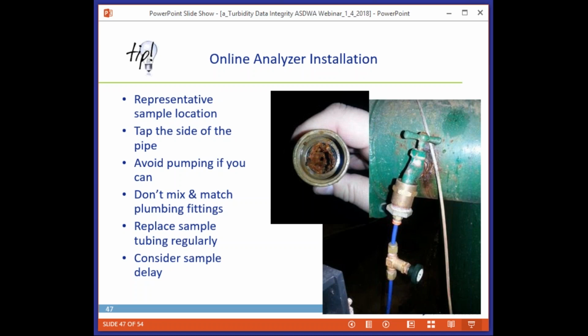Tapping the side of the pipe is clearly recommended over the bottom, where you may get sediment, but even more importantly than the top of the pipe, where you tend to get air accumulations, which can lead to some erroneous turbidity readings. If you can, it's ideal to avoid pumping. That's not always an option for people. Don't mix and match dissimilar metals. So this is a real example here. You can see that's pretty occluded.